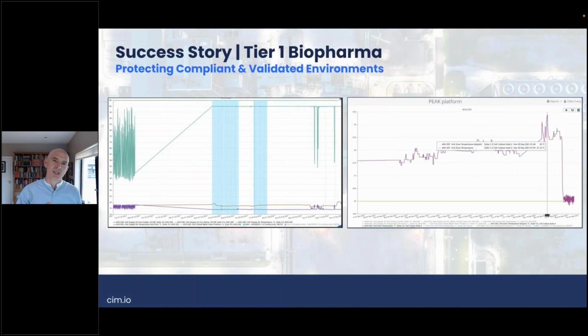And then I want to talk about some success stories, if you like, or some stories about how the BMS alarm didn't pick up issues that potentially would have become a problem for the site. And apologies, this is very graphy here, but on the left-hand side, the green squiggle line is the chill water valve on a coil in an air handling unit. You can see it goes from modulating, albeit it's essentially hunting here, which is another problem, up to maybe 100%, and it stayed at that 100% maximum valve position open, which is maximum cooling, for a sustained period of time, and it couldn't achieve the supply air temperature or the zone temperature in the space.